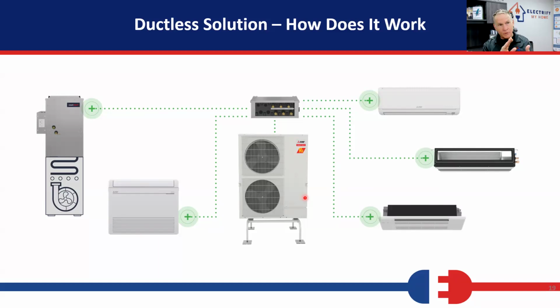You have to, when you install them, put the right amount of refrigerant in it. You need to weigh in the refrigerant for the additional line set, and you need to make a note somewhere. And sometimes these big systems like this can have 18 or 20 pounds of refrigerant in them, which you have to recover it all out and weigh it all back in. So you know it's right. You can't charge these type of systems just with your gauges like you can a single stage. But if they don't leak, they're way better, right?